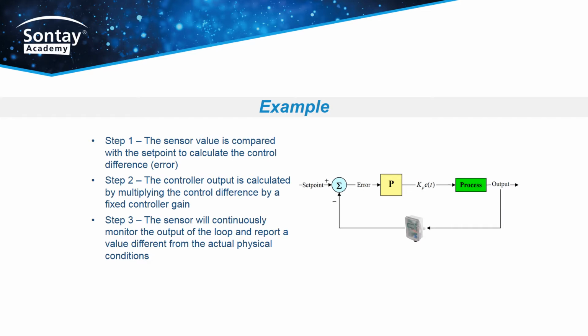Here is an example. In step 1, the sensor value is compared with the set point to calculate the control difference, or the error. If the sensor reading is inaccurate, then the calculated control difference will be incorrect, possibly causing a control action when none is required. Step 2. The control output is calculated by multiplying the control difference by a fixed controller gain. The controller gain is essentially an amplifier, and an incorrect sensor value will result in an even larger inaccuracy in the controller output.